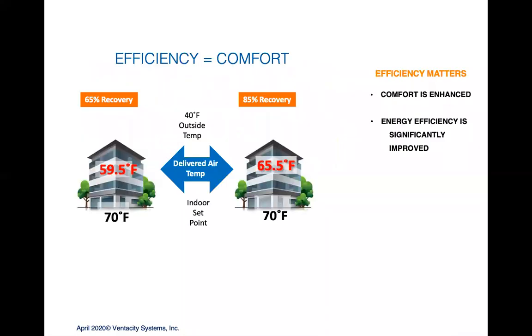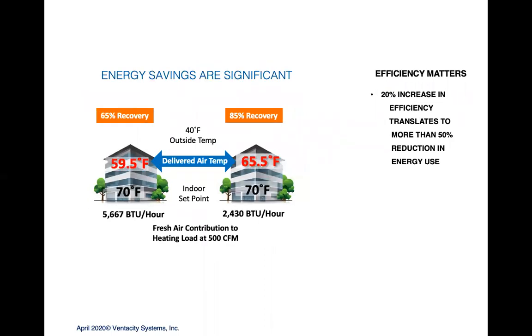So looking at that, I want to compare conventional heat recovery or energy recovery ventilation on the left, typically 65 to 70% as North American commercial ERVs, HRVs operate, to 85%, which is a passive house level of efficiency on the right. And on a 40-degree day, that's the difference between bringing in 59.5 degrees versus 65.5 degrees. So from a comfort perspective, that's a big, big difference. If you take that from an energy perspective, that 20% increase in efficiency is a very, very dramatic difference in energy.